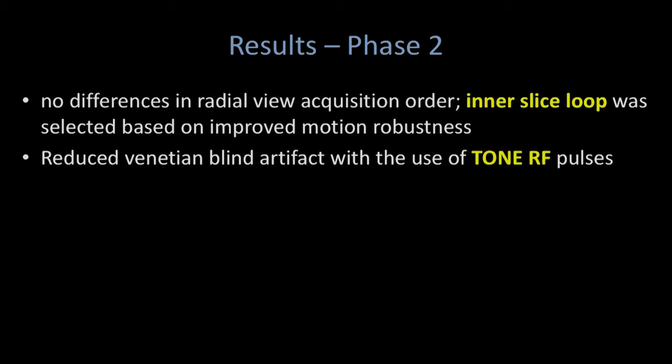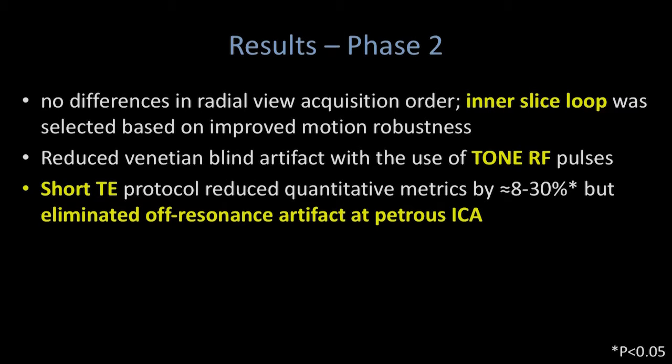We found that Venetian blind artifact was reduced using tilted optimized non-saturating excitation pulses. That's not a great surprise here; these pulses are used with 3D time of flight.